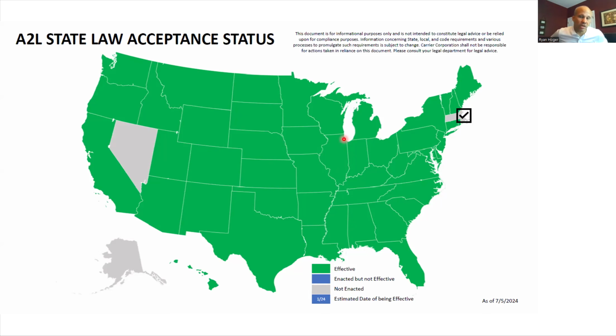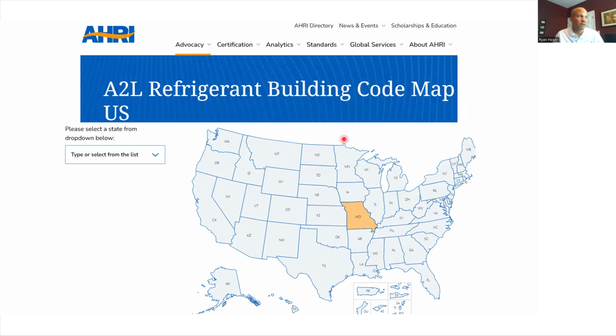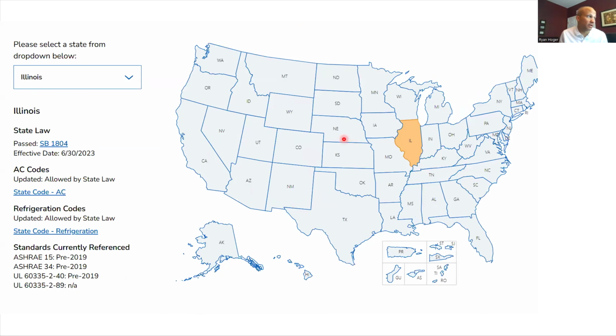So that means, like most of you know, if you work in the city of Chicago, if you had more than 30 pounds of charge on a circuit of A1s, R-410A, you had to have a relief valve installed. Well, with A2s and hence A2Ls, that limit becomes 6 pounds. If you have a 6 pound refrigerant circuit, which is most systems, you have to install a relief valve, which is a couple thousand dollars, right? Rules like that tell you the state is allowing it, right? So here's the language for Illinois. Here's the law for Illinois, SB 1804, that requires the municipalities to not prohibit A2Ls, but they can add restrictions to make it harder to do it.